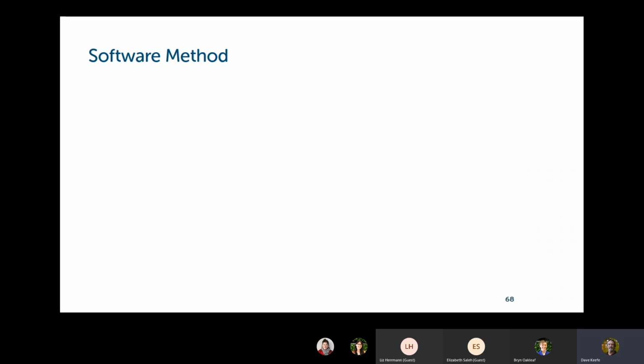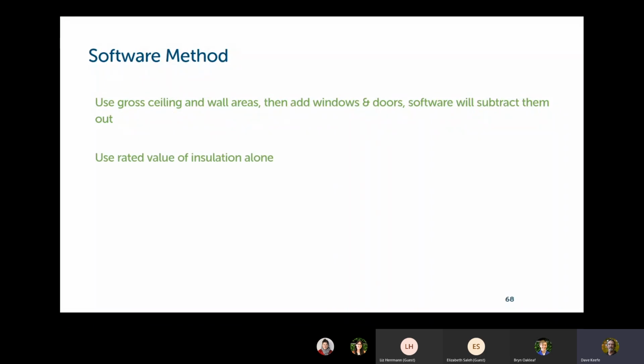So the things to remember for the software method are: use for ceilings and walls the gross area, and then the windows and doors will be subtracted out automatically. Use the rated value of the insulation alone. This is a pretty common question. For instance, somebody will say, well, what if I build a 2x4 wall and I put in fiberglass batts that are rated R11? What's the R value of that wall? And that's a very reasonable question, because the only number given there is 11, and that wall is not R11. That wall has batts in it that are R11.